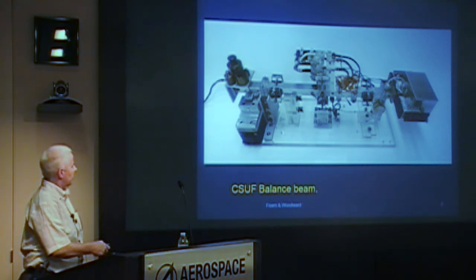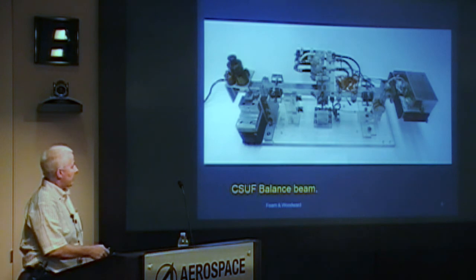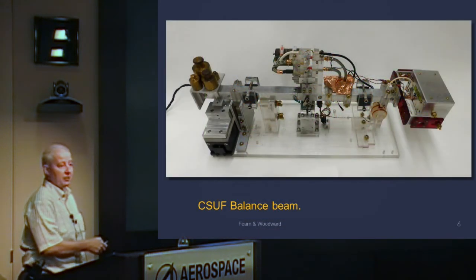And here, of course, is the damper. So it's a magnetic damper of the same type that Martin uses. It's just neodymium magnets in there. We also have coils. These coils are only powered if we want to test out the force and calibrate the force of the system. So I know most people have seen this before. It's just for the people that have not seen it.